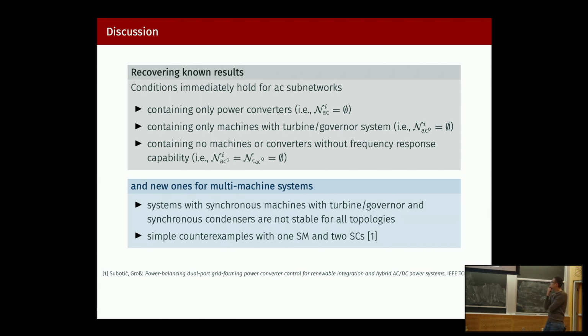And then there are also things that even the existing results do not capture. One interesting case, at least to me, is that if you have something called a synchronous condenser - basically a machine that doesn't have a turbine attached to it, just there to provide voltage support - there has been a huge debate around whether we can use grid following converters that just do maximum power point tracking plus a whole bunch of synchronous condensers to get a stable system, because then we have the spinning mass, a notion of frequency, and kinetic energy storage.